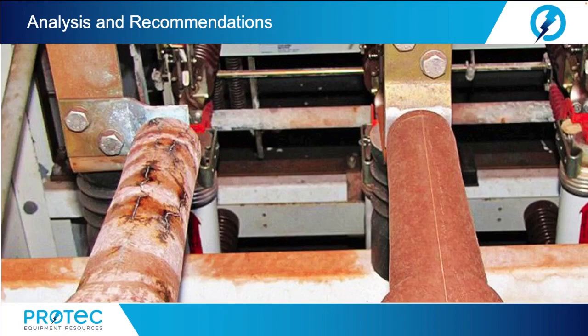Partial discharge testing is utilized to determine insulation condition and an early warning of impending failure. However, many sources of background noise can be present, including conducted noise from process loads, radiated noise from nearby electronic equipment or radio transmissions, and actual PD reflections coupled to the test object from other components.